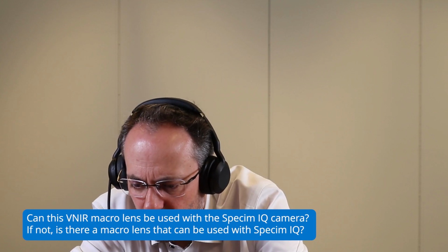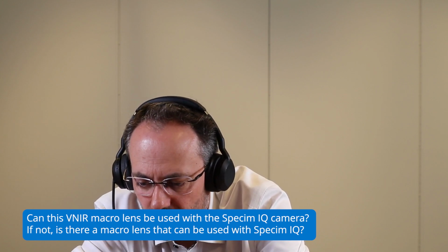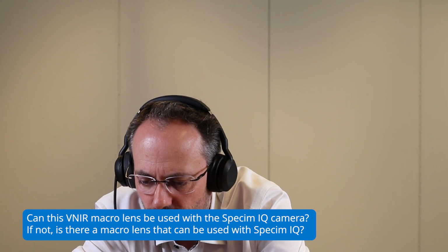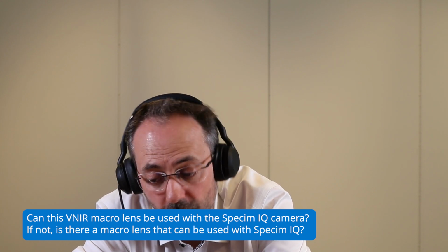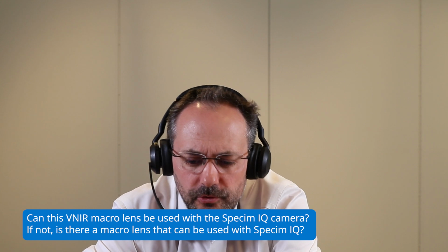Can this VNIR macro lens be used with the Specim IQ camera? No. If not, is there a macro lens that can be used with the Specim IQ camera? Unfortunately, no. In the IQ camera, the lens which is there is specially designed to accommodate the optics in there, because in the IQ, in fact, you have 3 cameras. You have the viewfinder to know roughly what you are looking at. Then there is a hyperspectral camera and there is a focusing camera. The focusing camera and the hyperspectral camera need to use the same optical path. So the lens has been designed to accommodate these things. So no, it cannot.